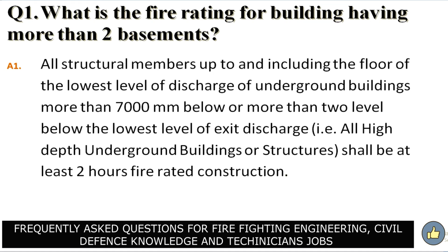Question number 1. What is the fire rating for building having more than 2 basements? Answer. All structural members up to and including the floor of the lowest level of discharge of underground buildings more than 7,000 millimeters below or more than 2 levels below the lowest level of exit discharge, that is, all high depth underground buildings or structures, shall be at least 2 hours fire rated construction.